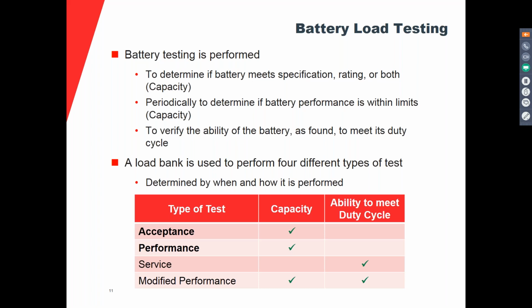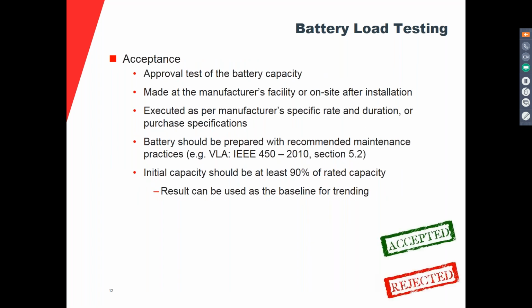So these reasons to test define four types of tests, which are called the acceptance test, the performance test, the service test, and the modified performance test. These will provide the capacity, except the service test. The service test is the only test that can verify the ability to meet the duty cycle of a battery. In this presentation, we're going to be talking mainly about the acceptance and the performance tests, which we're defining now.